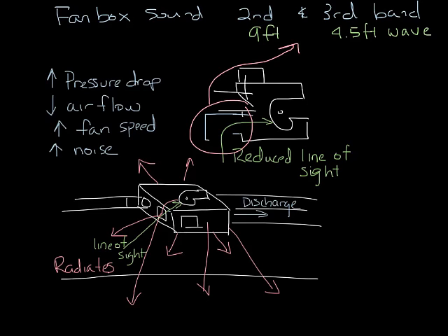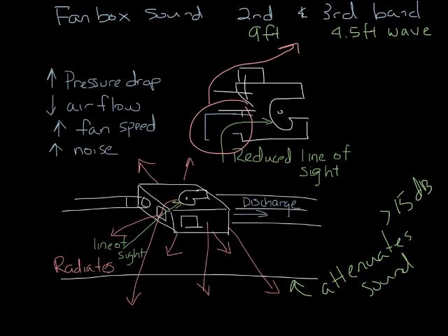Like with the single duct box, the ceiling will attenuate a lot of the fan box radiated sound, but if you have an application that has no ceiling, be sure to select your boxes without a ceiling, because a ceiling can give you 16 to over 35 dB reduction, and if you're not going to have a ceiling, you'll want to know this when you do your sound calculations.